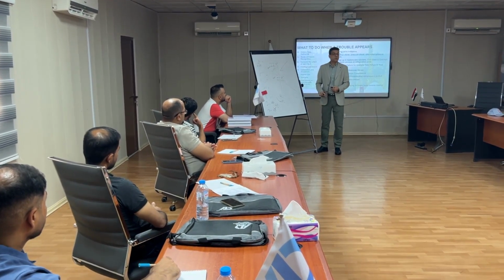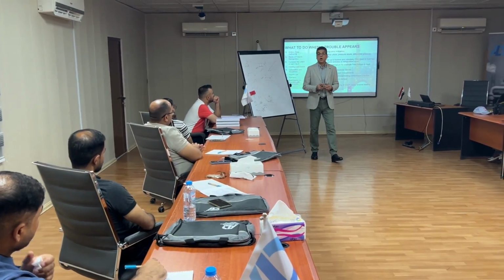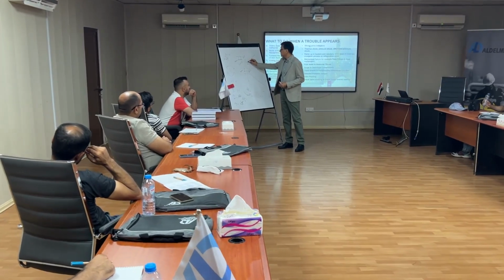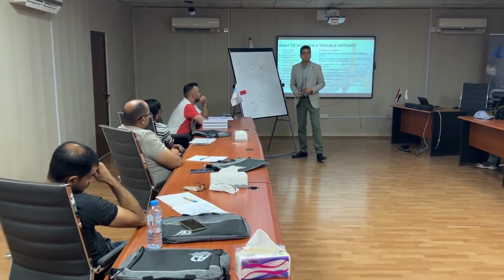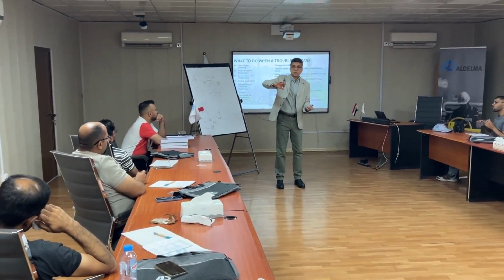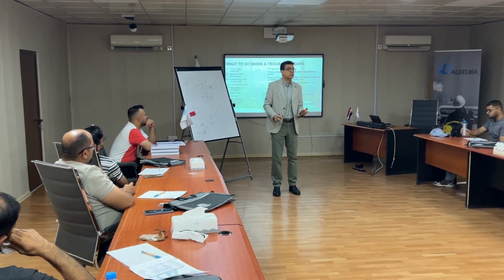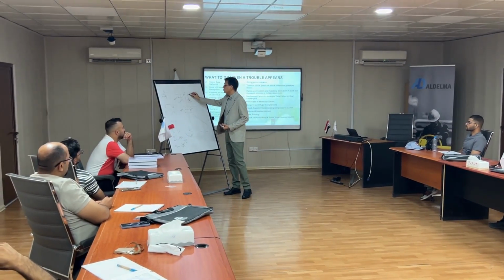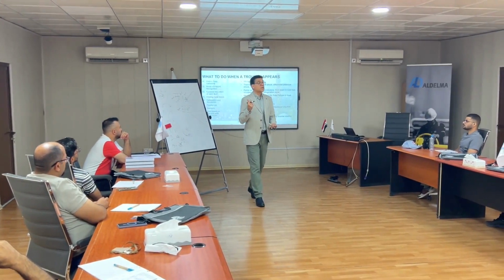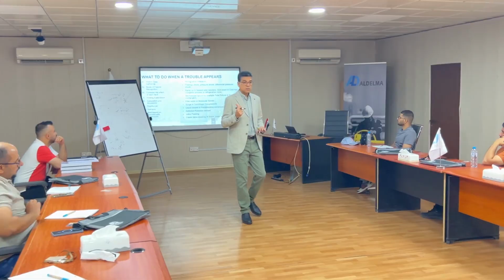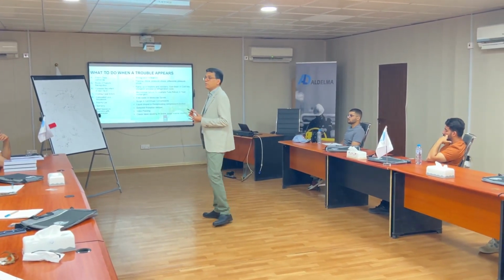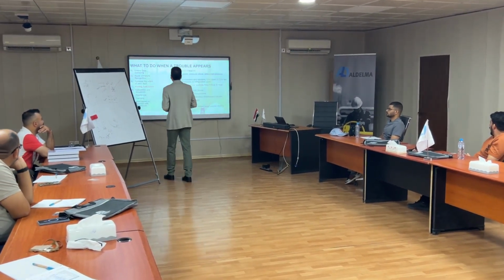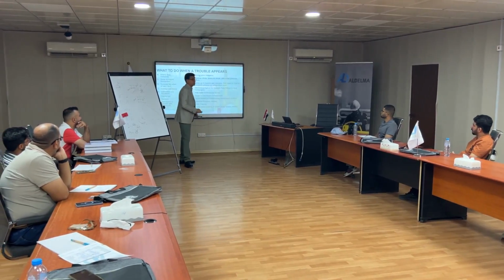For example, for the heating media, when we are working with hot oil, the maximum temperature increase is 40 degrees centigrade per hour. When we want to increase the temperature, we are only allowed to increase by 40 every hour. Yes, you can increase it by 80, but you reduce the lifetime of your equipment. Leakage, low efficiency, fouling, coking, and cracking are the side effects of this. And also the pressure shock.